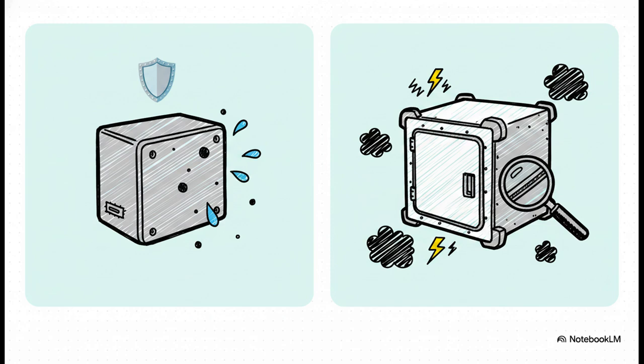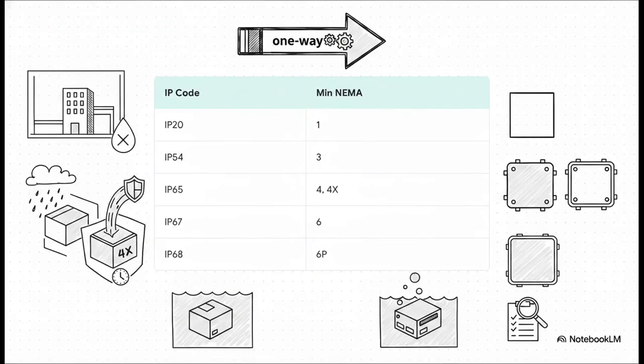It mandates things like gasket aging, specific construction practices, and, this is the big one, corrosion resistance. And because NEMA packs in all those extra durability requirements, you literally cannot just take a NEMA rating and perfectly map it backward to an IP code. It doesn't work that way. It's strictly a one-way street here. You can take an IP code and translate it into its minimum required NEMA standard to hit those criteria.